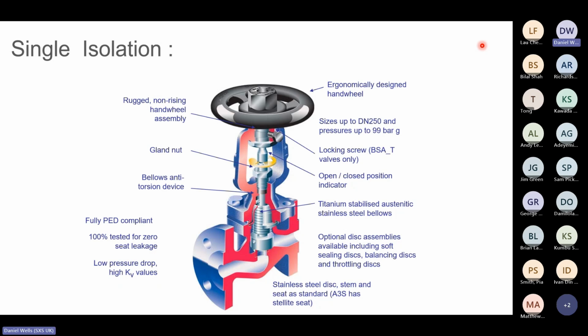The other reason is a ball valve and a butterfly valve, they've got very, very smooth sealing surfaces. So they're more susceptible to erosion, especially if we've got a poor condition of steam. So it's very, very difficult to guarantee safe isolation. So we prefer to see a piston valve or a globe valve because they're very, very slow operating.